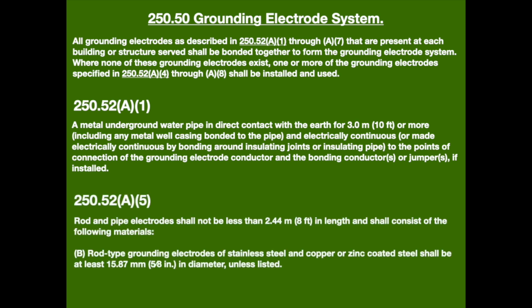Rod and pipe electrodes. Rod and pipe electrodes shall not be less than 8 feet in length and shall consist of the following materials. Rod type grounding electrodes of stainless steel or copper or zinc coated steel shall be at least 5/8 of an inch in diameter unless listed.